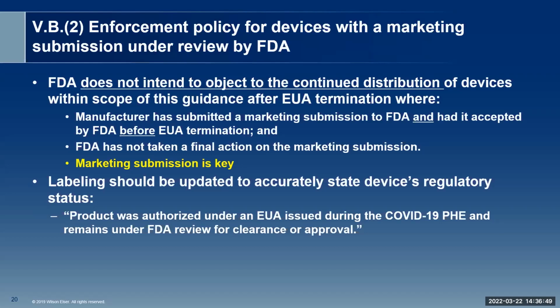And also, the FDA will enforce a labeling update to accurately state the device's regulatory status. The FDA suggested some language in your updated labeling, which says the product was authorized under an EUA issued during the COVID-19 PHE and remains under FDA review for either a 510(k) clearance or an FDA pre-market approval.